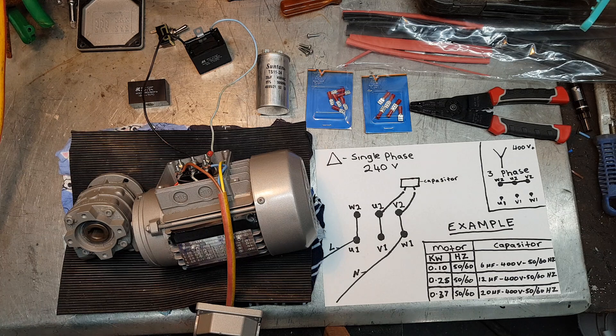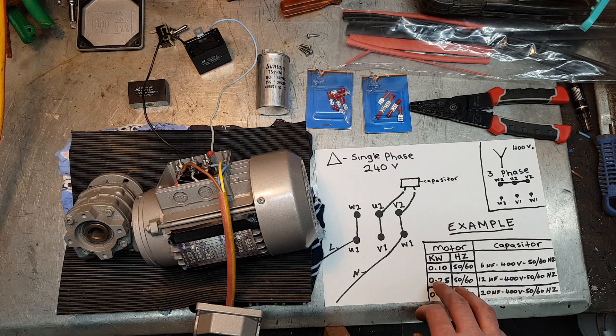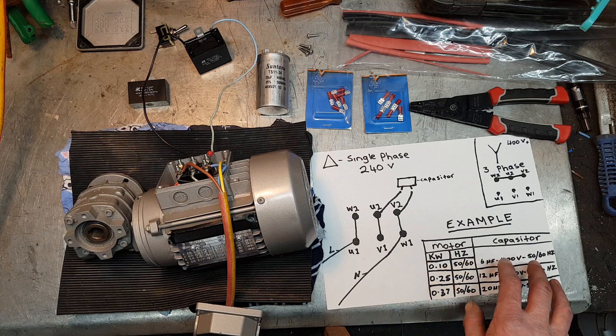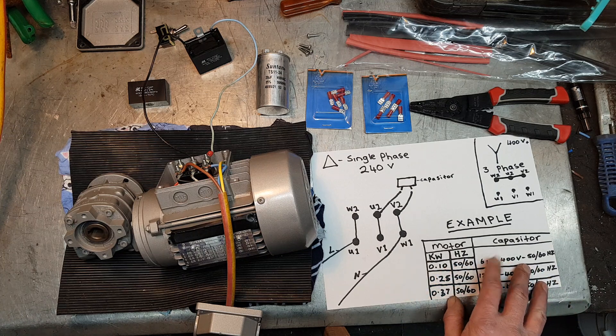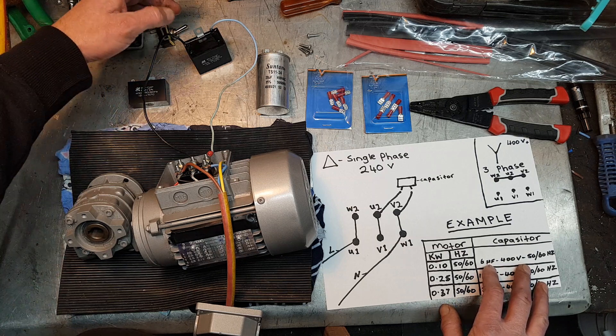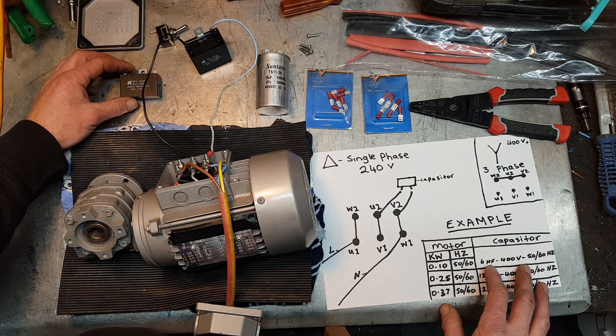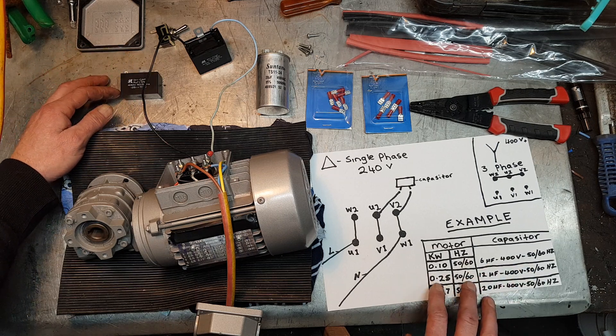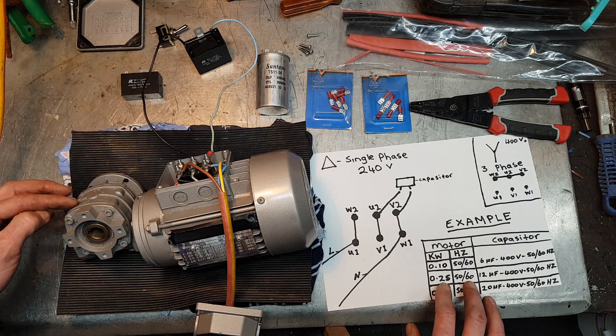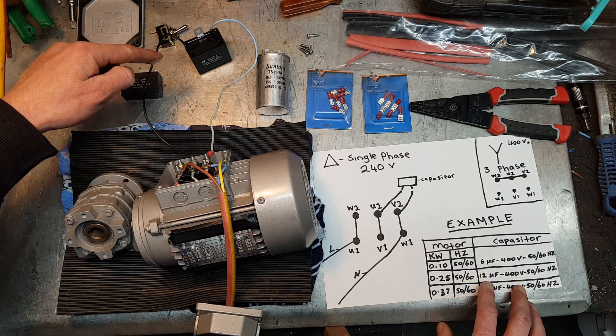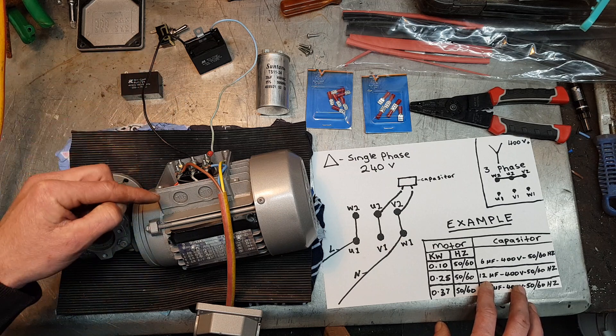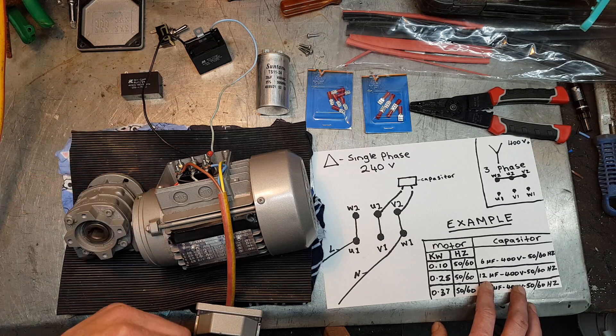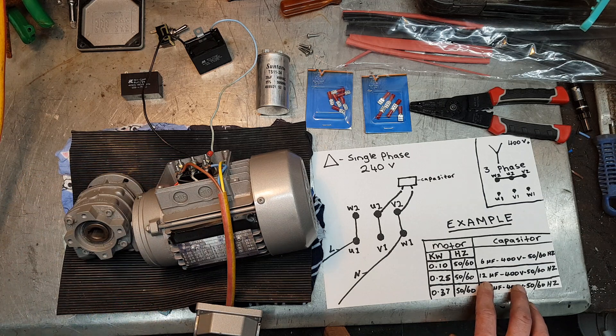We can do it just by the capacitors that we use, but you can't use too big of a capacitor. I've worked out basically for 0.10 kilowatt you need about 7 uF, so I could only buy a 6. But because I'm using a 0.25 for the motor, I basically doubled that and just bought a 12. It is a bit less, but that's fine. It doesn't overheat the motor. If I run a bigger size on this, the motor will heat up and you can burn your motor out.